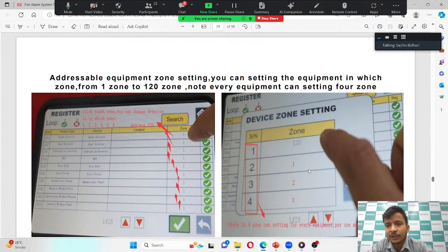Addressable equipment zone setting. You can set the equipment in which zone, from zone 1 to 120 zones. Note every equipment can be set for 4 zones. You can add the devices in a zone, and you can make up to 120 zones in this panel, and these zones are defined in four different types, so there are up to four serial numbers, and in one serial number you can add up to 120 zones. Sorry, I think I was wrong in this one. In one zone, you can add a maximum of 120 devices, and we have a total of 4 zones.